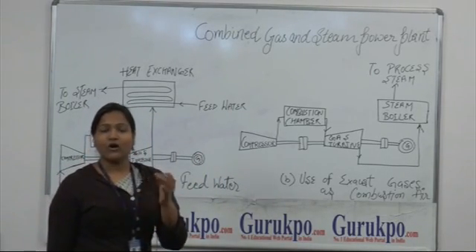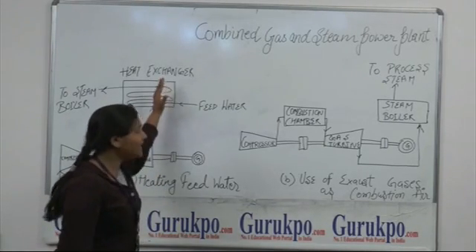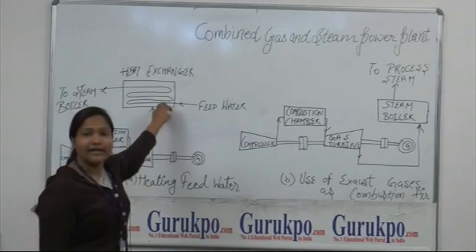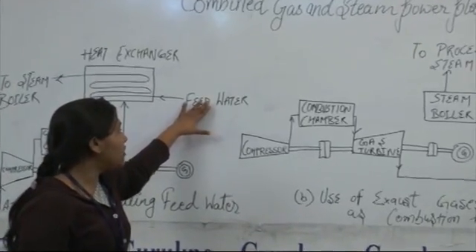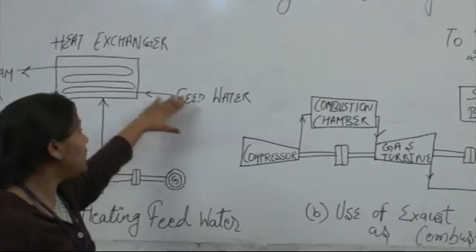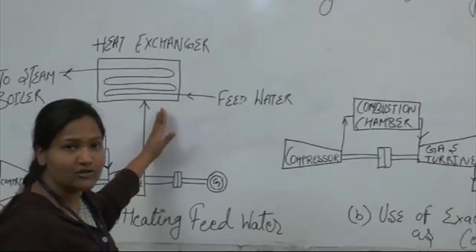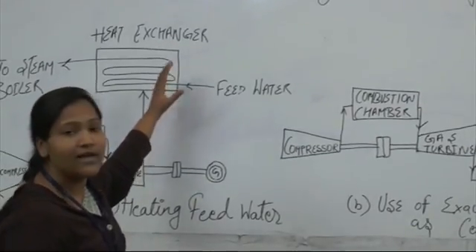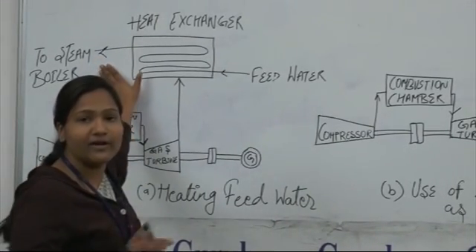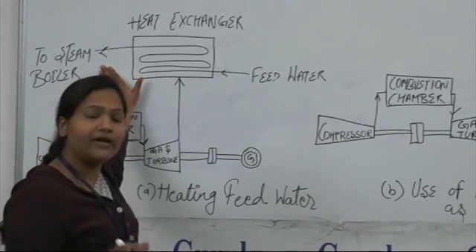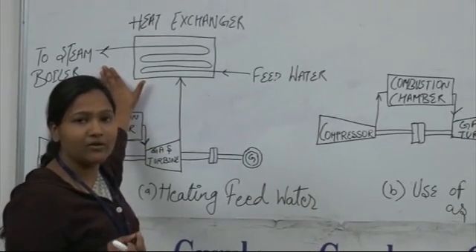Now that hot and high pressure exhaust gas is also useful in our heat exchanger of a steam power plant. In the heat exchanger of a steam power plant, feed water from a cooling tower or the condenser is fed to the heat exchanger. Here, the heat of the gas turbine power plant exhaust gases is utilized to heat the feed water, and the heated feed water is now provided to the steam boiler where it is boiled and converted into steam, and this steam is then expanded on the steam turbine where it can produce electricity.